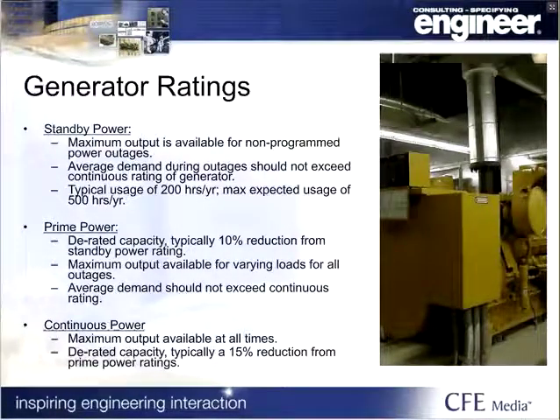So when we're talking about how long the generator is going to run for, and not only how long, but at what load that generator is going to run, we start to think about what kind of rating my generators are going to be. Are they standby, are they prime, or are they continuous power? Basically, the engines are relatively the same, but a prime at a certain level would be a standby at a certain level and a continuous at a certain level. I'll show you an example in a second. Basically, a standby would be on demand, but you're not considering running that at full peak load for a continuous period of time. So if you are going to be a load shed site, you may consider going to prime or continuous.